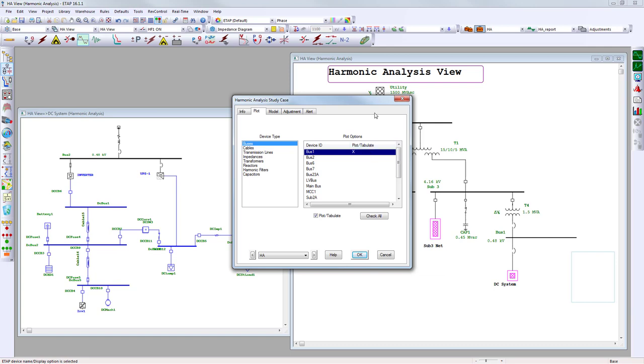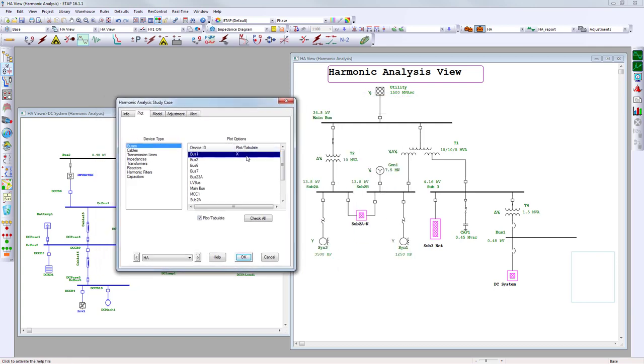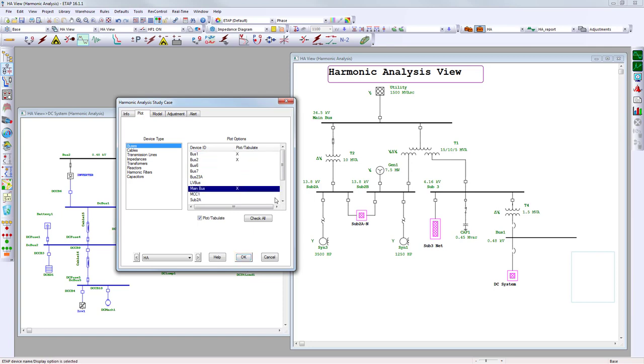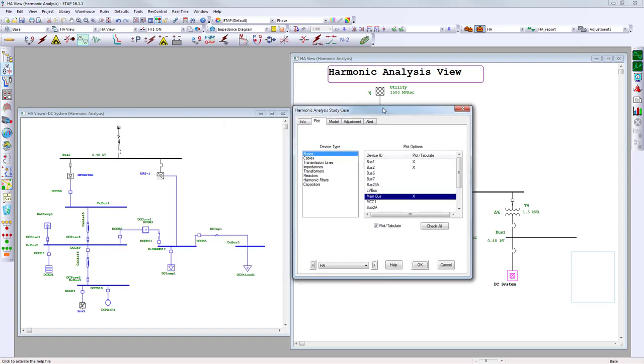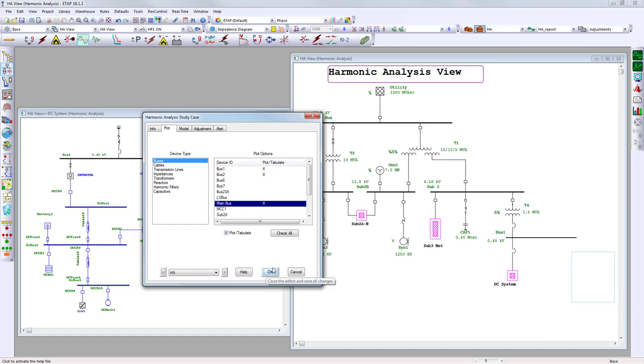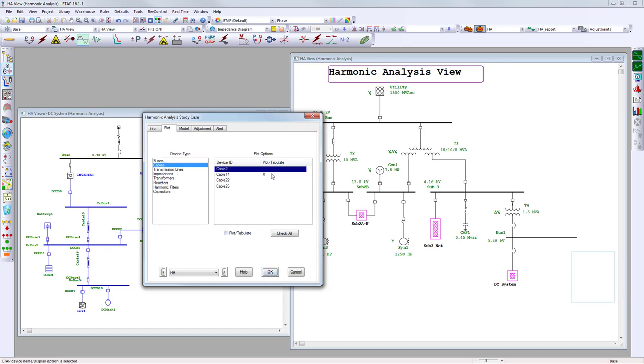The study case controls what information is displayed on the single-line diagram and plots. If everything is selected by default it may get crowded, so focus on specific locations: the main bus as the PCC, bus number one, and bus number two on the DC composite network on the line side of the inverter. I'd also like to see cable 14 — selecting branches such as cables, transmission lines, or transformers to see total current distortion through them.